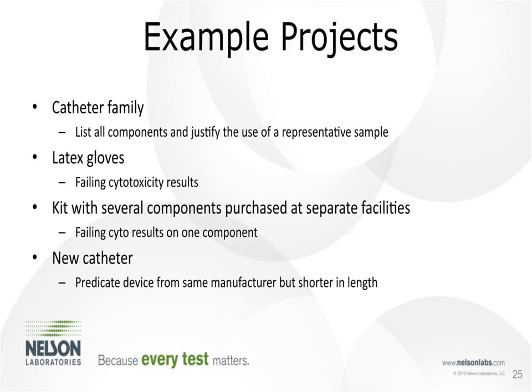And so you want to make sure when you have a family and there are so many different colorants that could be used, that all of those colorants are assessed in your evaluation. What happened with this project is we helped to identify a representative sample. We looked through all of the materials and all of the different colorants and the different sizes, and we picked a worst case scenario, and then the manufacturer made a sample of a device, not one that they marketed, but of a device that they were going to use to do all of their testing on.